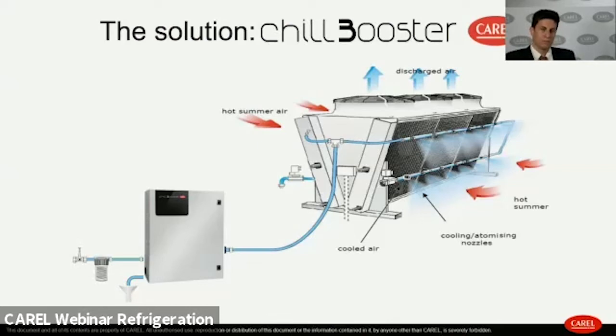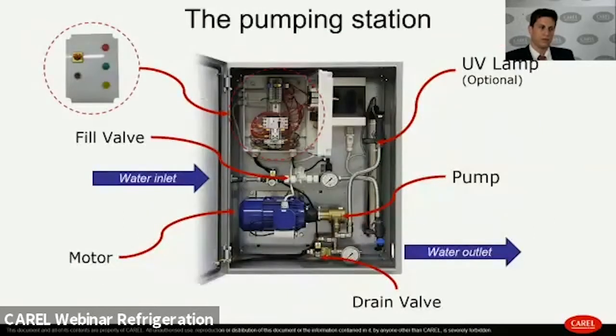The way to use chillBooster is quite simple. Whenever the chiller or the condenser or gas cooler has a drop in efficiency, the system can be activated in order to spray and cool down the air and restore the design condition. The warmer and the drier the air is, the more effective the solution is, since the drop in temperature could be higher. Let's see now how the system is composed. I mentioned that we have a pumping station and we also have a distribution system.